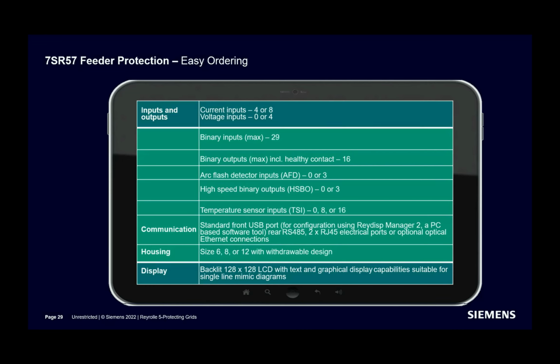Now, lastly, motor protection, 7SR57. This device comes with 4 or 8 current transformer inputs depending on the requirement for motor differential protection. And again, CT only and CT plus VT versions. Maximum binary input quantity is 29 and maximum binary output is 16. Exceptionally, only for 7SR57 with size 12, a TSI module is available with 16 temperature sensor inputs. The others will have 8 temperature sensor inputs. So 16 temperature sensor inputs are exclusive for 7SR57 for large motor applications. And so, as a result, we have 3 case forms available for 7SR57: size 6, size 8, and size 12.